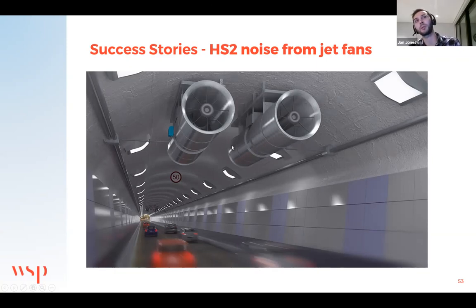And there's also a sort of natural ventilation, an opening to outside, such that hot air could rise and dissipate. These fans are very noisy, and there's not much you can do to attenuate them or make them quieter, essentially. So in this example, we were able to consider the noise impact, which even with the maximum mitigation that could reasonably be achieved was over the design requirements for the noise level on the platform area.